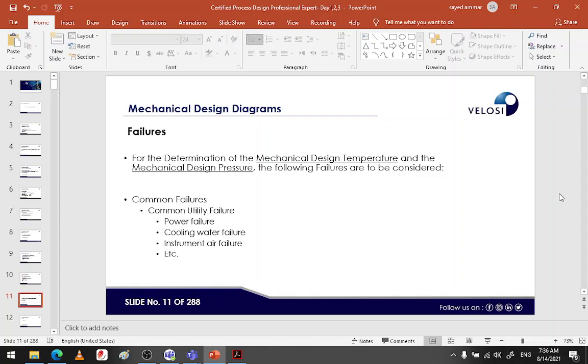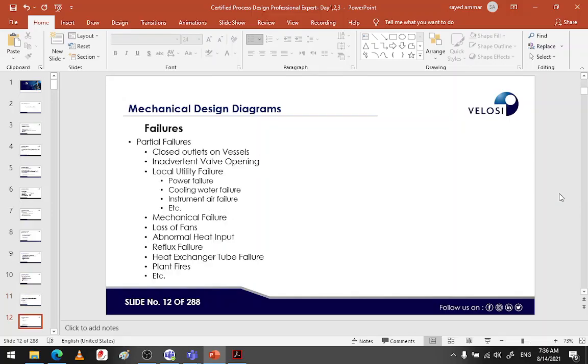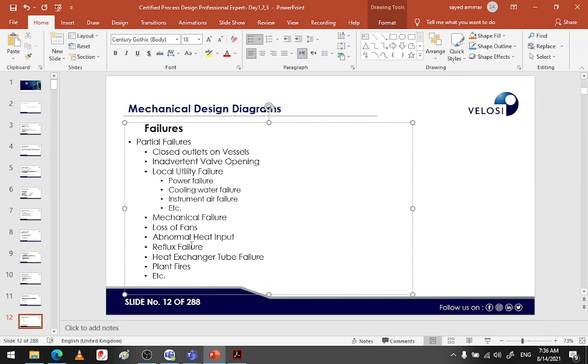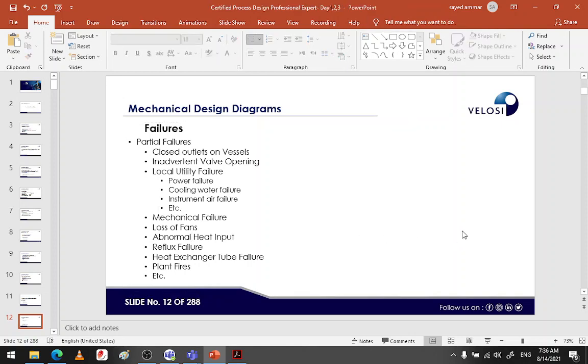That is the most common failures you are searching for. There's a lot of partial failures like closed outlet on the vessel. We're going to use this in the depressurization. Then we have the loss of fans and mechanical failures and abnormal heat input. We are going to challenge all of this during our P&ID design.